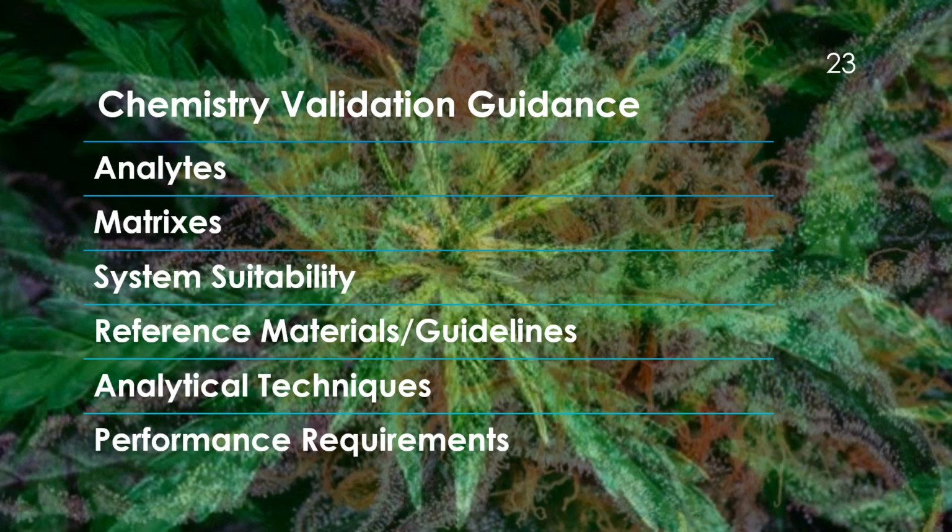While we're using ICP-OES and ICP-MS now to do metals testing, at some point we may use a different type of technology, and so we want to be open to that. Others, though, are more restrictive and say it has to be an LC method or a GC method. And then what are the performance requirements? What's the acceptance criteria for an LOQ or an LOD, RSD repeatability, relative standard deviation of reproducibility, percent recovery, those sorts of items.